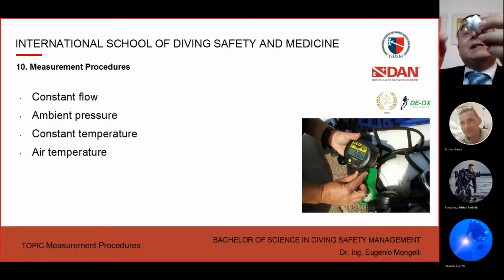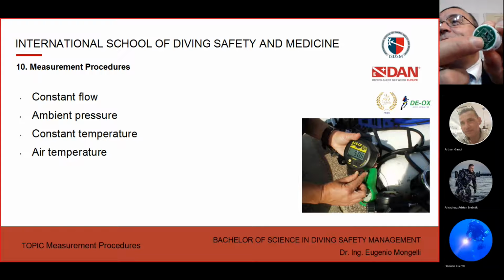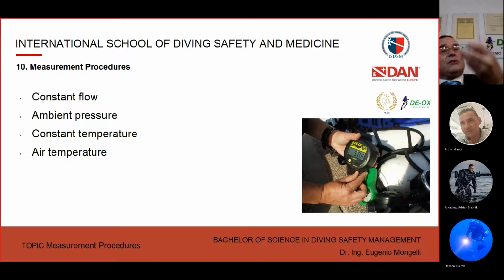All the sensors, I forgot to tell you, also have electronics inside. This is the electronic of a sensor. They have some components here. One of the components is a thermistor, so it is a thermal compensator. So it makes the output of the sensor stable, whatever the temperature is, because it changes the resistance, and then adds or reduces the resistance, and then gives you a stable output. But it needs time, you know. It's not immediate. So if you have a flow from the cylinder that is 10 degrees different in temperature from the sensor, you must wait for the sensor and the thermistor components to chill down to the same temperature, otherwise you have a wrong analysis.